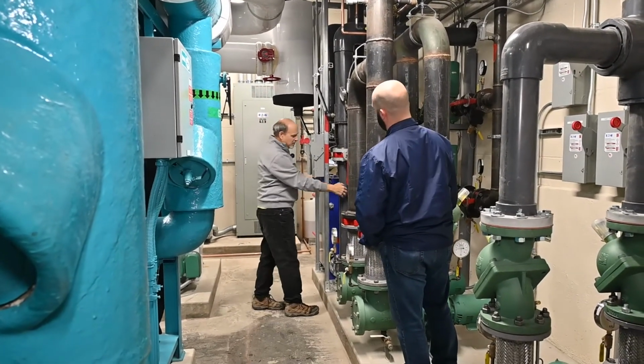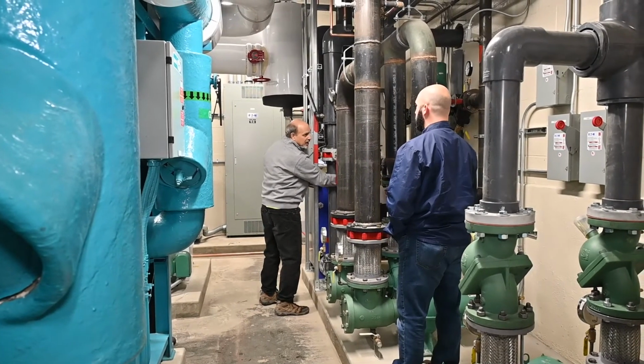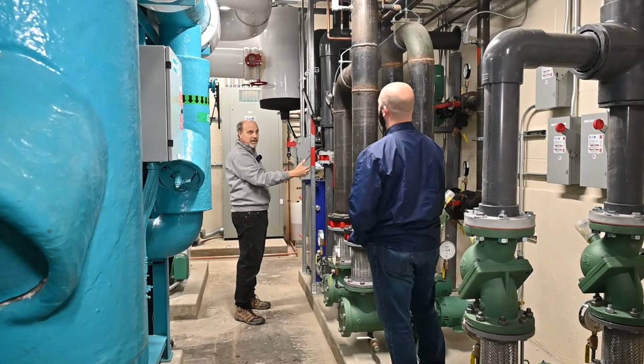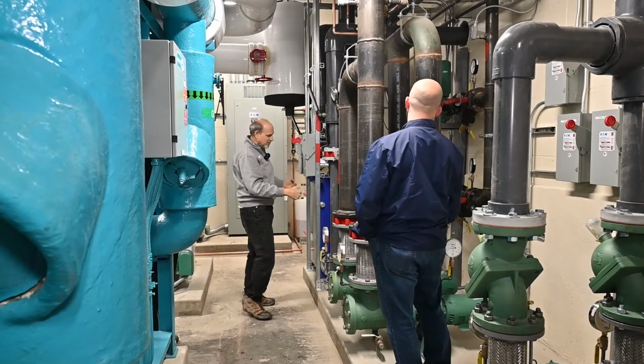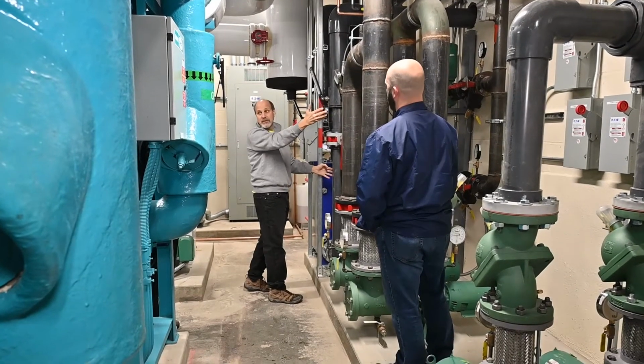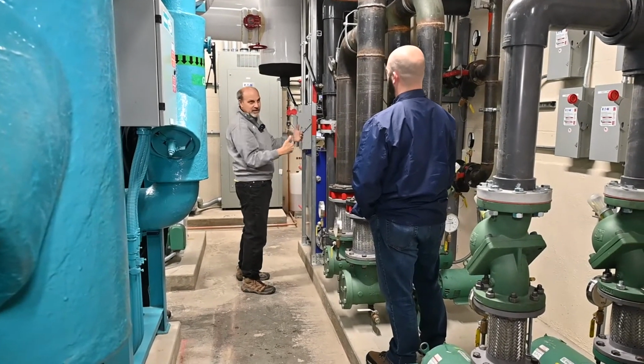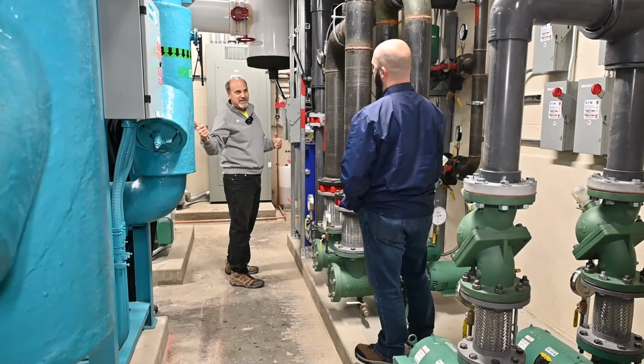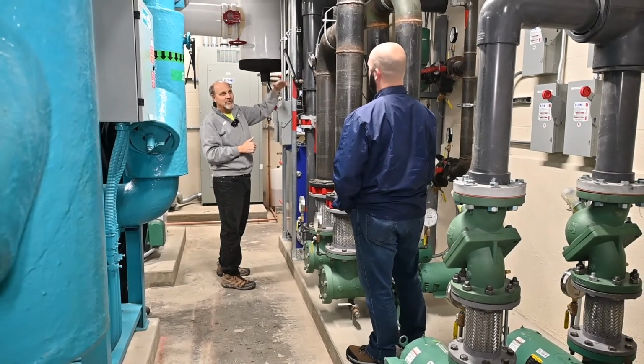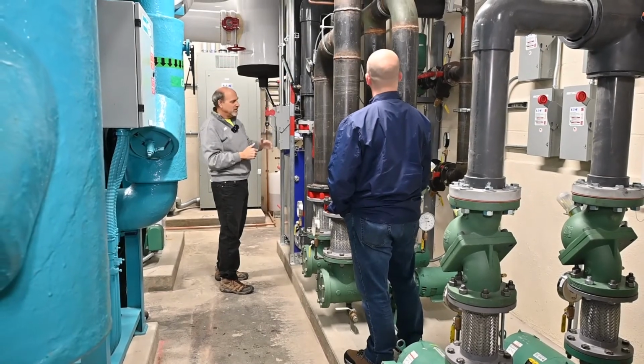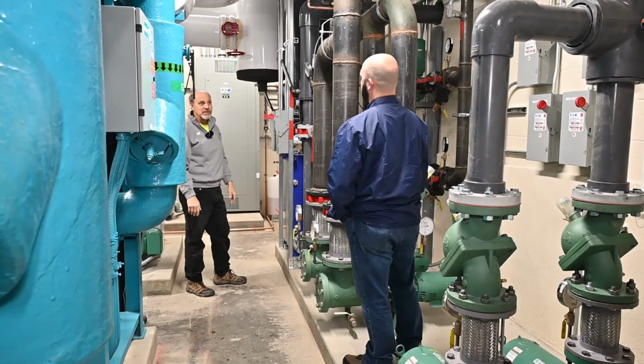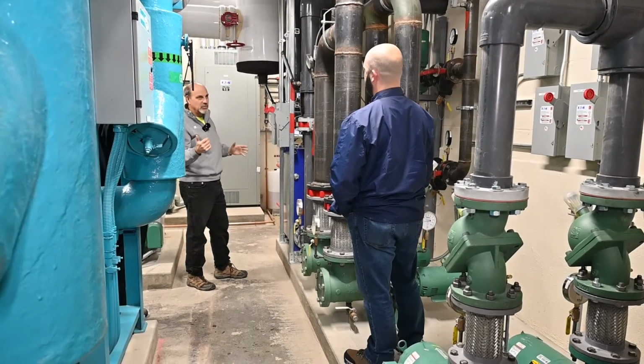So this heat exchanger on one side, the steel pipe side, has glycol on it, warm glycol from the chiller system. The other side is just water for your cooling tower. So what it's doing is exchanging the heat between getting rid of the heat in the chillers out to the cooling tower, and the cooling tower is doing its job. So in essence, that's just a standard cooling system for cooling the compressors.